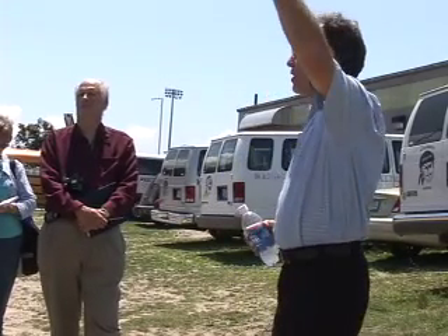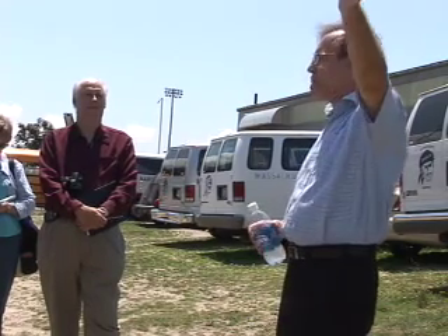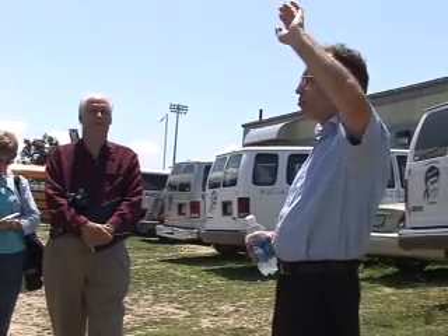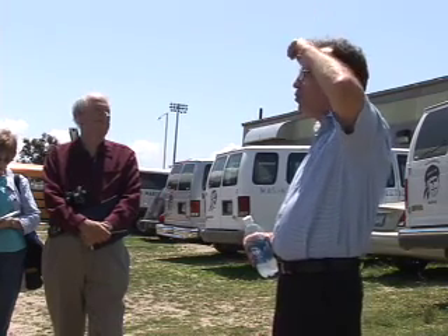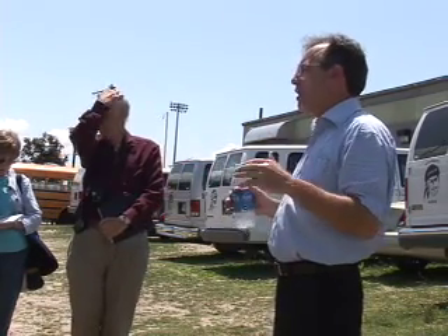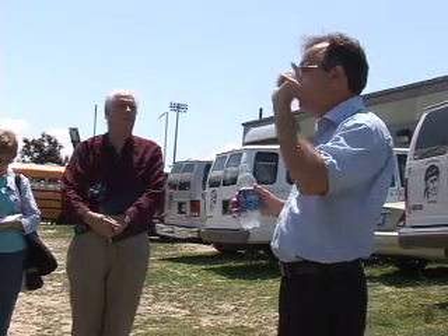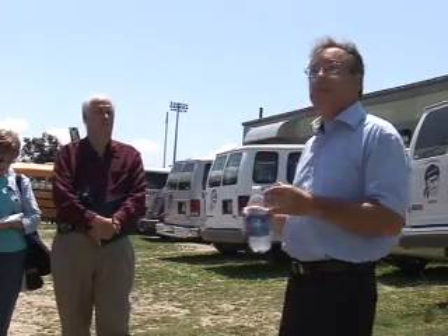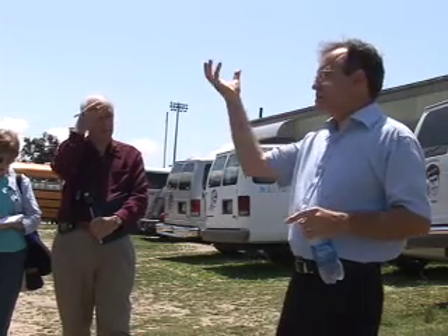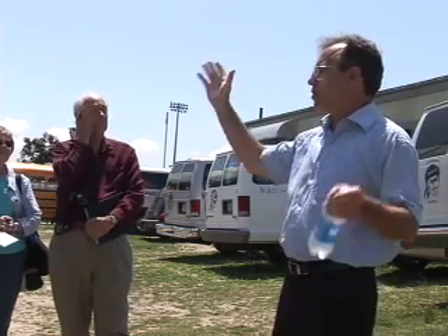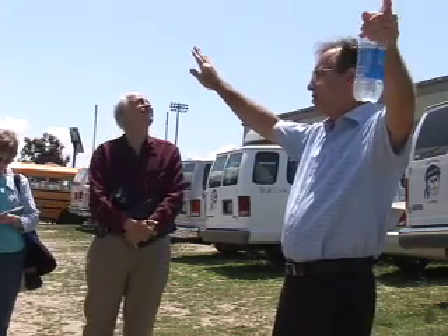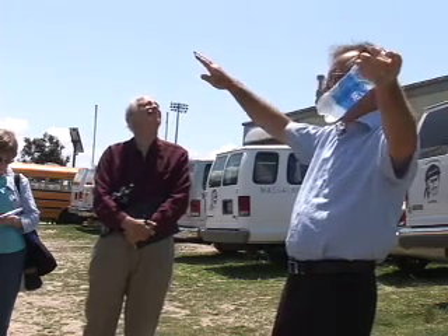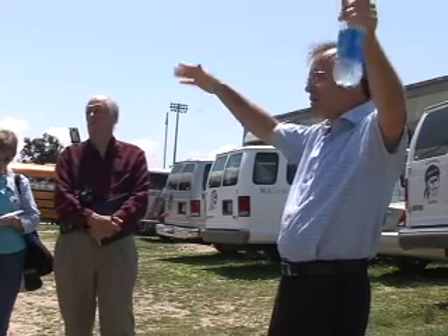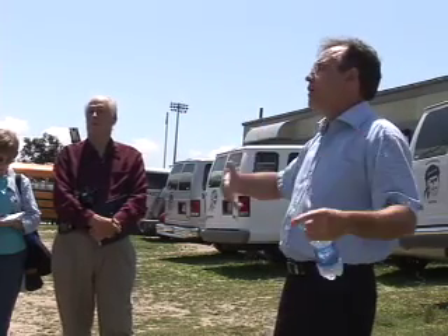You have a wind measuring instrument up there, you have an anemometer, you have a wind direction vane. It's all automatic, controlled by computer. When we get somewhere in the neighborhood of about 8-mile-an-hour winds, and we have it in the run position, the processor will say, okay, let's try to generate some power. There's a hydraulic system up there that yaws the machine. It turns it into the wind, but it also pitches the blades. When it starts up, it pitches those blades to about 45 degrees, so they're at maximum starting torque. So it gets that rotor rolling.